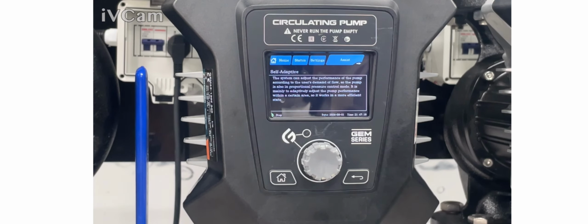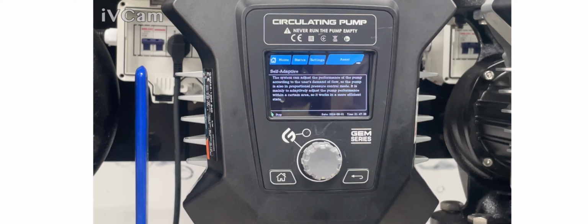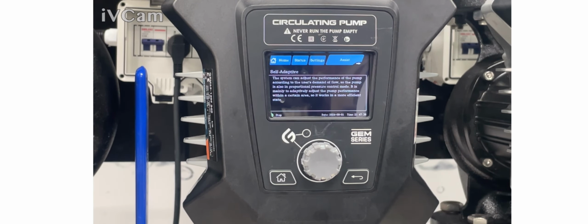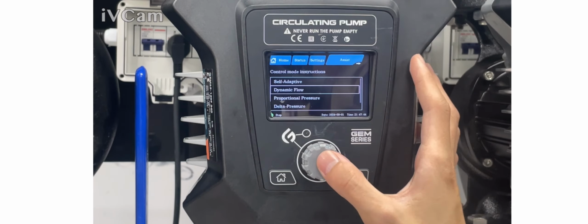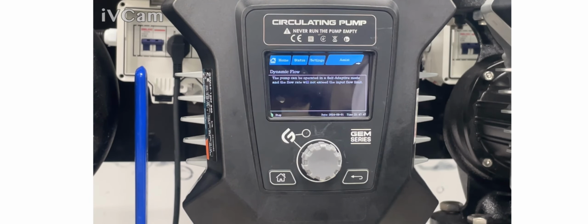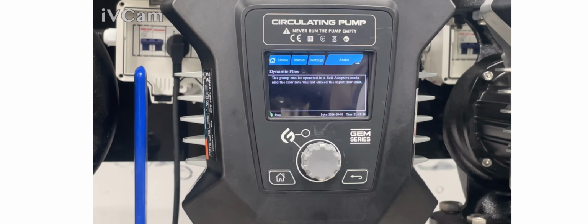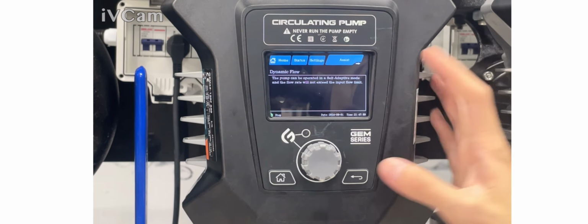First of all, it's self-adaptive. The system can adjust the performance of the pump according to the user's demands of flow. So the pump is also in proportional pressure control mode. It is mainly to adjust the pump performance within a certain area, so it works in a more efficient state. And next is our dynamic flow. The pump can be operated in a self-adaptive mode, and the flow rate will not exceed the input flow limit.